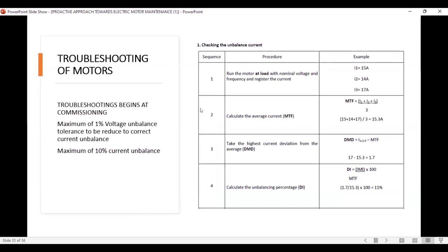Let's look at a typical example of motor current imbalance troubleshooting. Let's look at this motor. It has one phase drawing about 15 amps, another phase drawing about 14, another phase drawing about 17. Somebody will just look at these values and say, okay, the difference is not very wide, so the motor is okay. But it's prudent that after running your motor, you do the calculation. You must calculate and confirm and convince yourself that the imbalance is within the tolerable level of 10%.